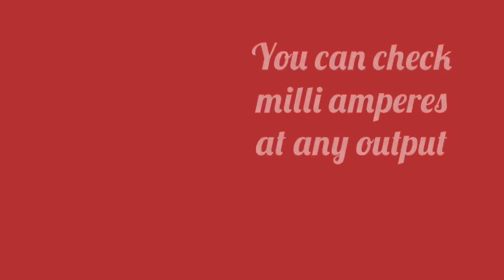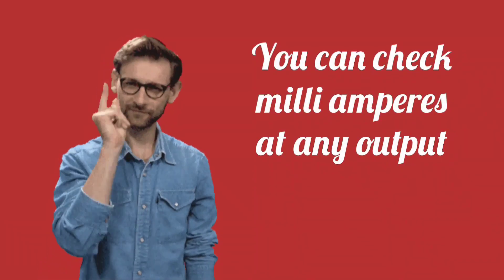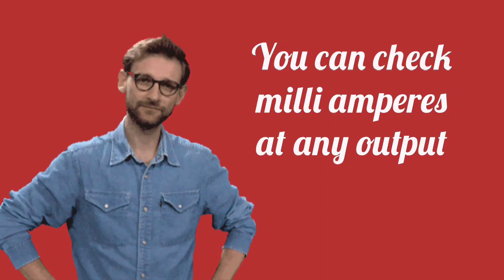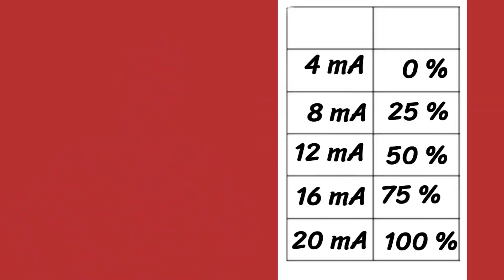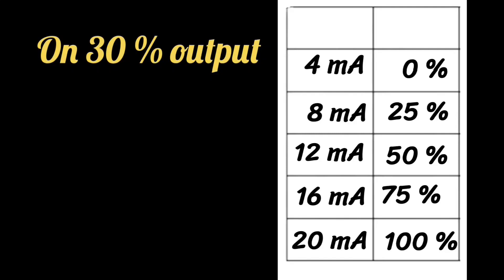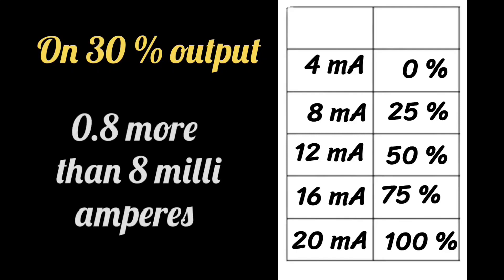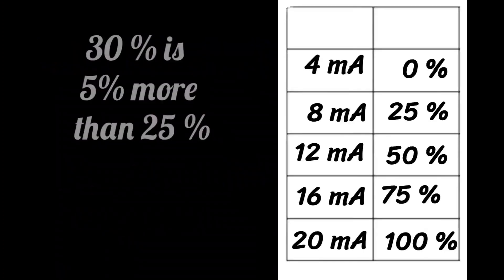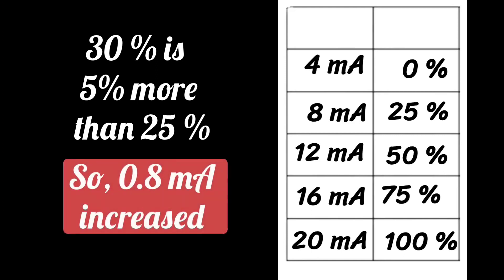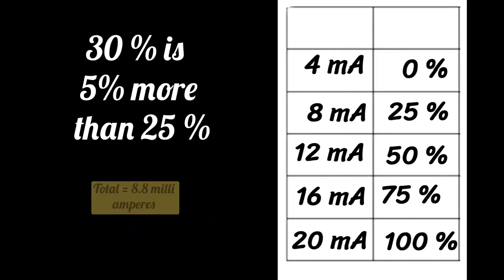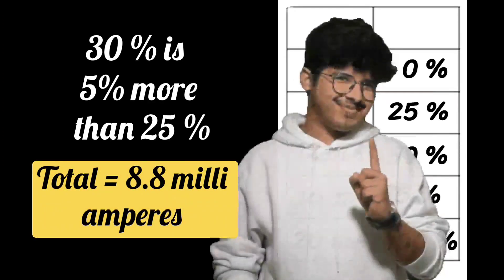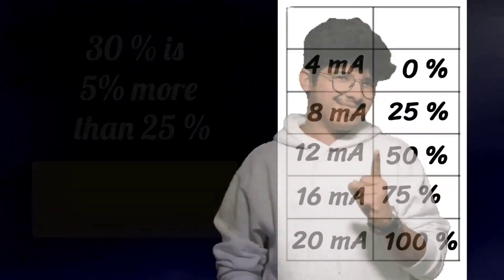Now you can check milliamperes on any output. For example, at 30% output, 0.8 milliamperes will be more than 8 milliamperes. 30% is just 5% more than 25%, so 0.8 milliamperes will increase and total we get 8.8 milliamperes. Isn't it so easy?